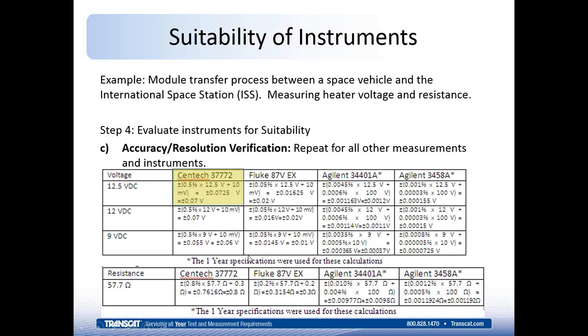All right, so now I've created a table here for each of the 4 instruments and each of the voltage measurements, as well as a table for the resistance measurements, and I've done that process we just went through of converting the accuracy statement to a tolerance in the unit of measure. And so it looks like a lot of information, but it's a relatively quick and simple thing to do. And here we show that first example of plus or minus 0.07 volts, again rounded to the resolution of the instrument at that range. And we've done that for every other reading as well.